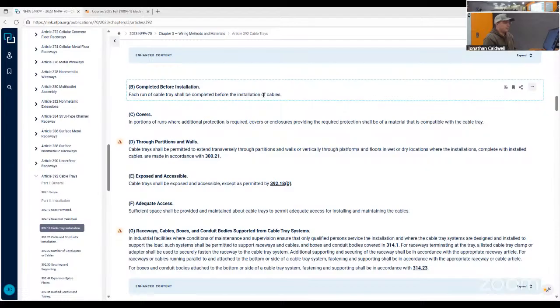We, out of Simplot, how can I put this? We've been slowly upgrading the electrical rooms out there at Simplot. So in order to be able to do all the work we have to do within a month or two, my coworkers can attest to that, we do work our asses off for this month or two. We have to run tray outside and then pull the cables and have them ready to go inside the MCCs. So technically, what we're doing is against code because that raceway is not completed, right? But in order to do it in a timely manner for that shutdown of the plant, we have to have those cables ready to be pulled into the MCC, and then we can complete the raceway inside the MCC from that point.